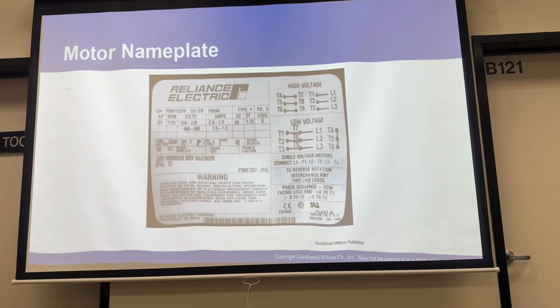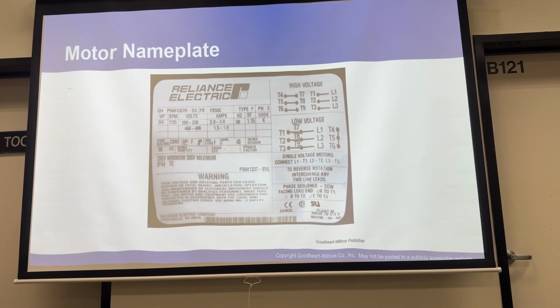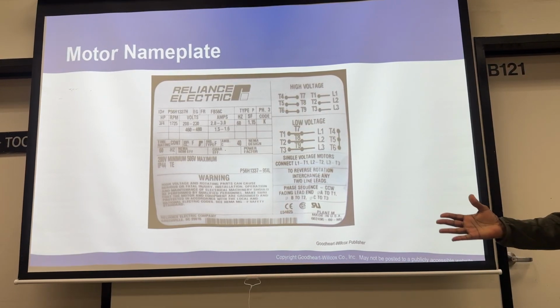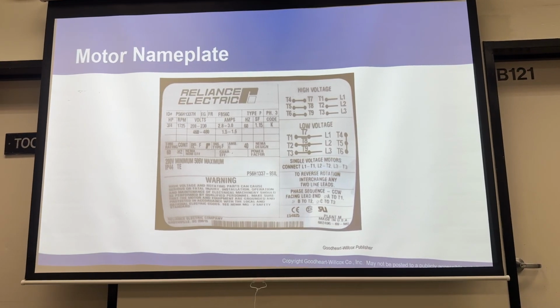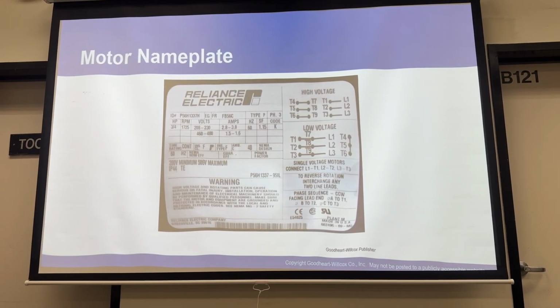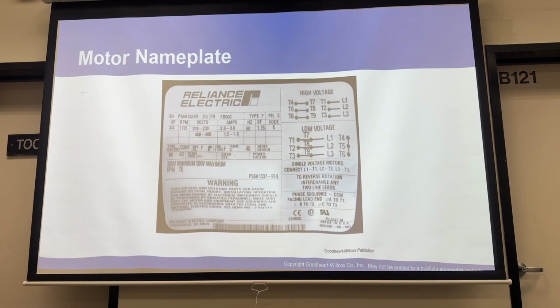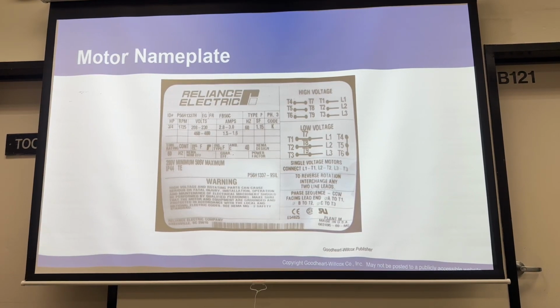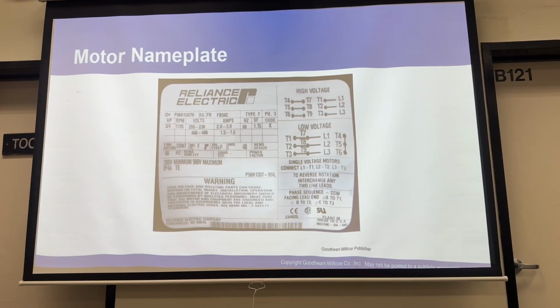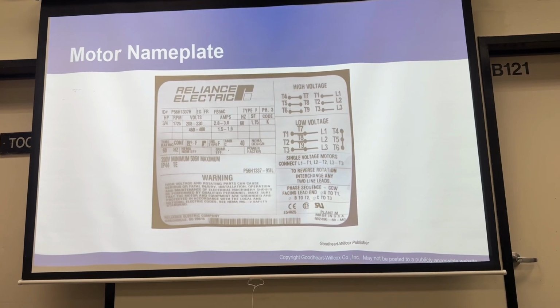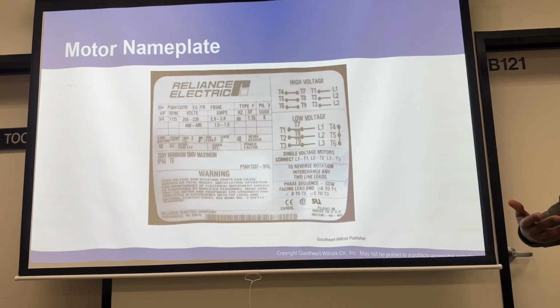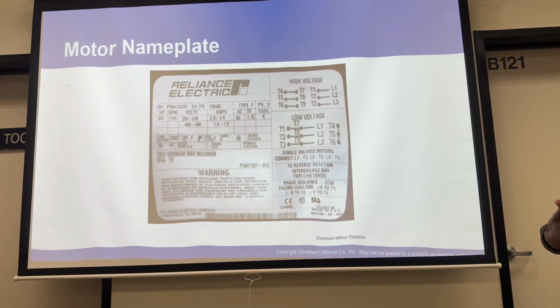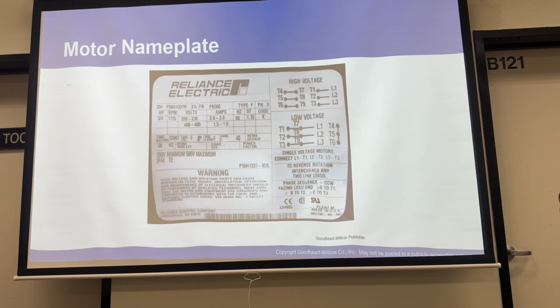So these motors are dual purpose motors. You can make it high voltage or low voltage. Instead of building a motor for two things, you just build one and use it either way. It's like a transformer — they use control transformers you can connect in series or parallel to make it high voltage or low voltage. Same principle here.